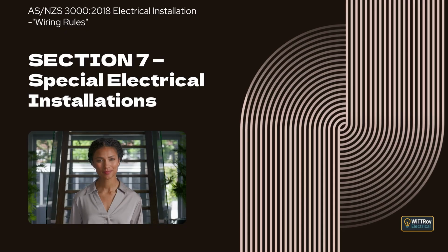Clause 7.2.8.2.2, segregation of cables for evacuation equipment. This clause explains that conductors supplying evacuation equipment must not be enclosed with conductors of different safety services or with conductors of any other wiring system. It explains that effective segregation can be achieved using divided ducts or trunking, physical separation of at least 50 mm or effective barriers, and by ensuring conductors of different safety services are not combined within the same multi-core cable.